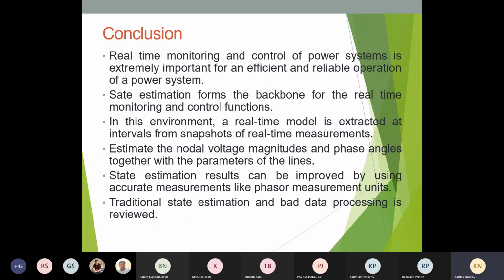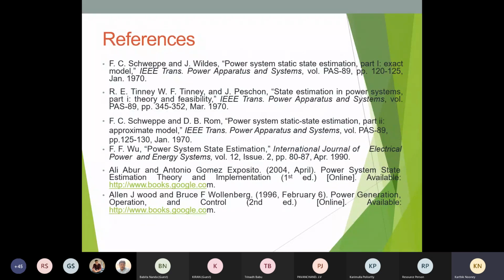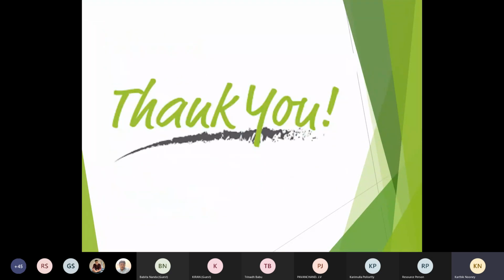What we conclude is that real-time monitoring and control of power systems is extremely important, and state estimation becomes the backbone. In this environment, a real-time model is extracted, namely IEEE 14 and 30 buses, and we have estimated the nodal voltage magnitudes and phase angles by considering all the input data of all the buses and transmission lines connected in the 14 bus and 30 bus systems. State estimation results can be improved by using accurate measurements like PMUs, and traditional state estimation and bad data processing is reviewed. These are the references.